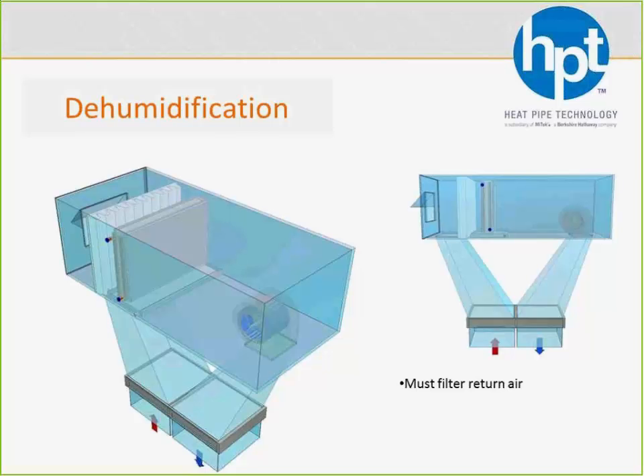But I wanted to show this because it's a little bit different, and there's more considerations involved. So one, obviously you've got to filter that air on both sides. The air is naturally going to be filtered on the supply side, but you're going to want to filter it upstream of the return side as well. But more importantly, in this type of setup, you're going to have a chance for some condensation, depending on where you are. If it's in a horizontal duct or in your air handler, it's a piece of cake. You have a drain pan. But if you've got vertical duct, it's a little bit more involved, but you still need to be able to drain that condensate away. So make sure if you have this type of setup that you account for some means of draining that condensation at the bottom of that vertical duct.